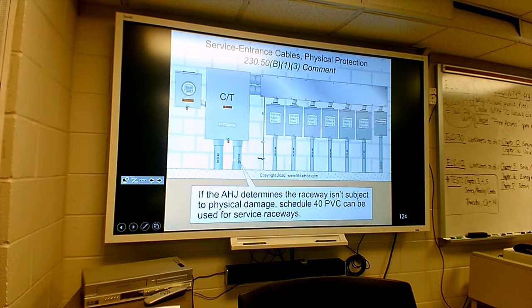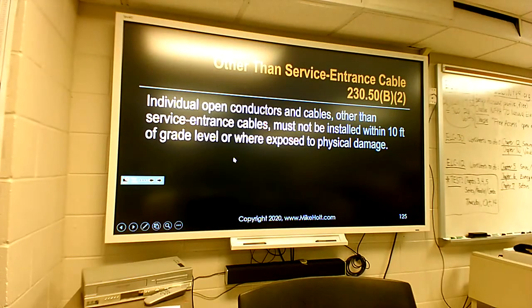That's what I'm here to buy a permit to do. And do you approve of all these materials for this particular job? And then let him go through what y'all discuss. He can tell you if he objects to something. He'll ask you questions like, is it subject to something running into the conduit? And then you answer those questions. Other than service entrance cable, individual open conductors and cables must not be installed within 10 feet of grade level or ground, or where exposed to physical damage.